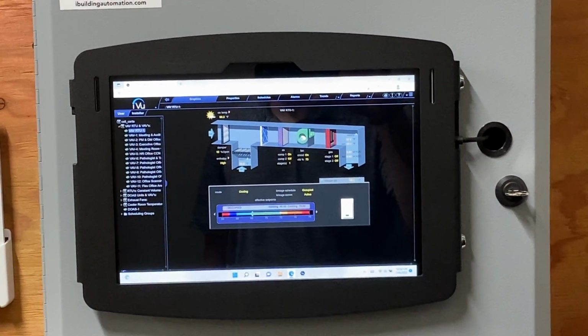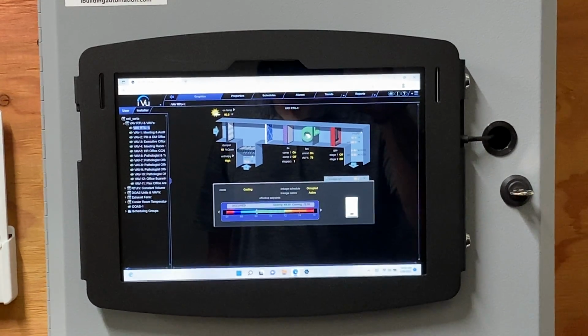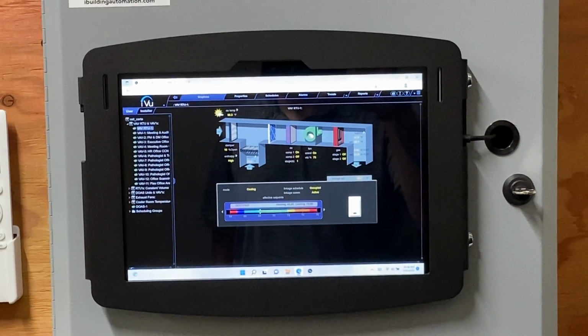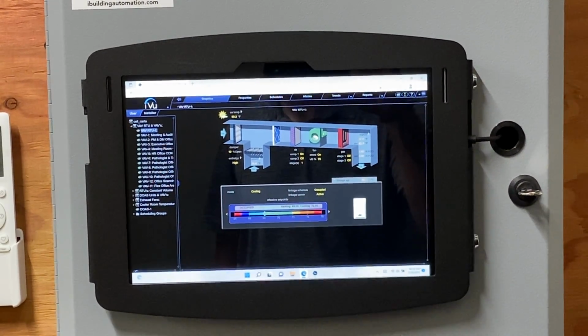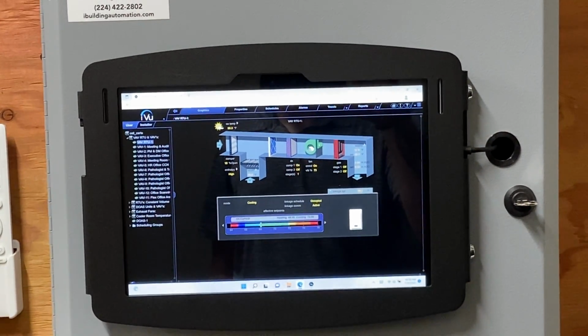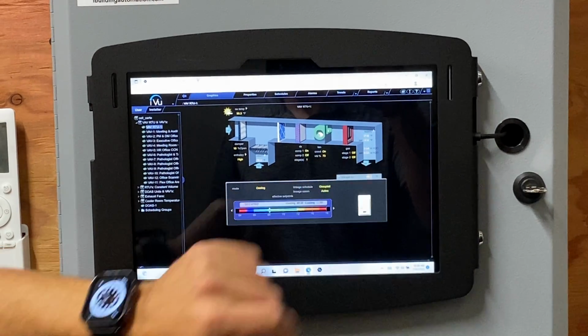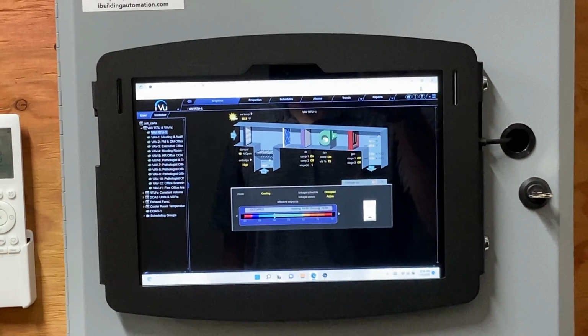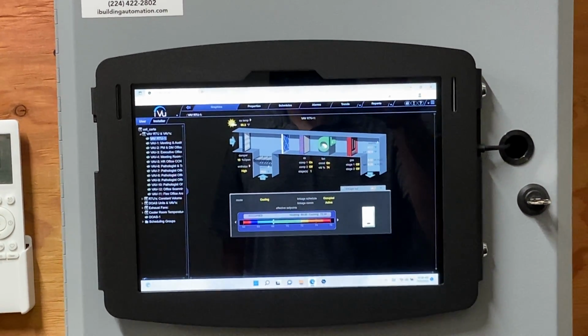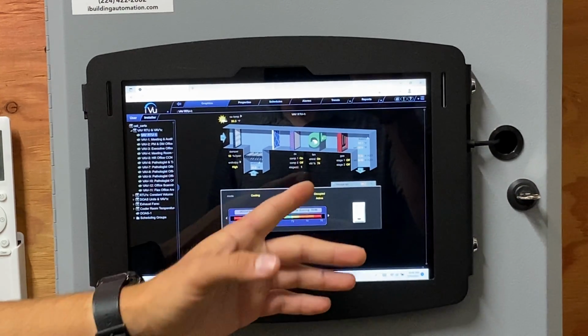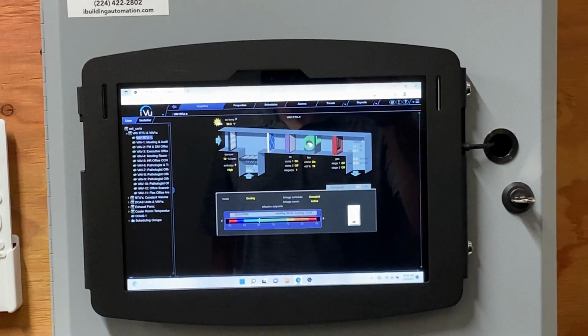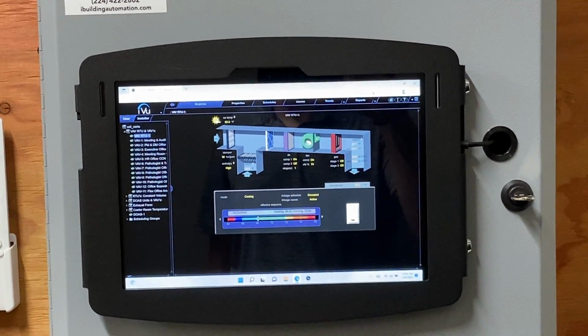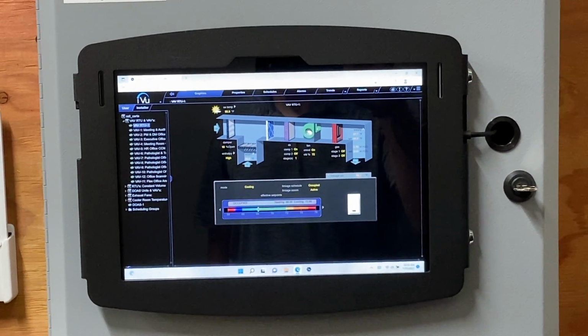It's not going to say, let's say it's really hot in here and you have both stages of compressors, mechanical cooling running at the roof - it's just going to say cooling. Through this screen, you're actually going to navigate and find out, do we have 2 stages? Is our fan at 100%? Are we at maximum cooling capacity? These are values you'll check to see what the unit's producing.